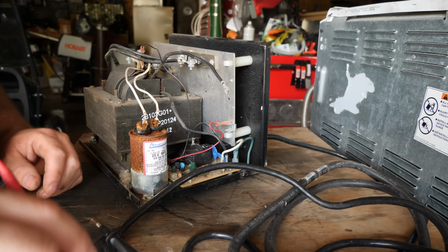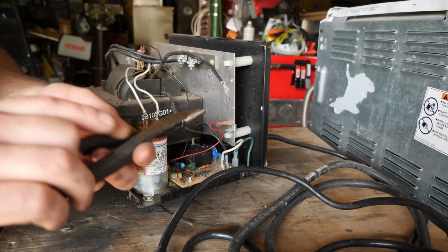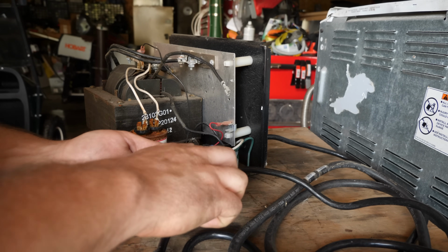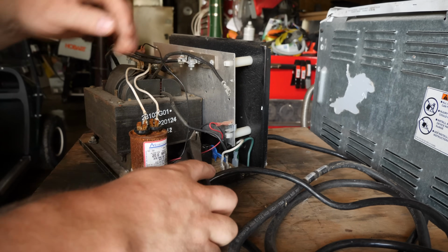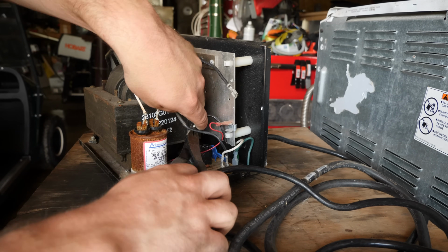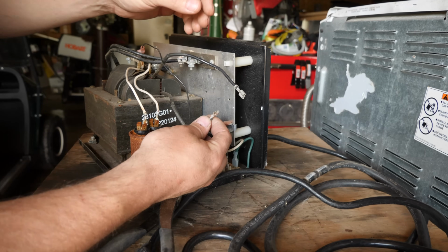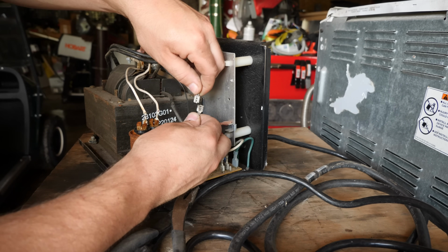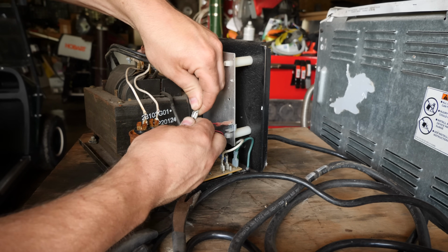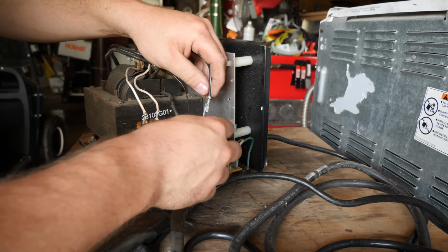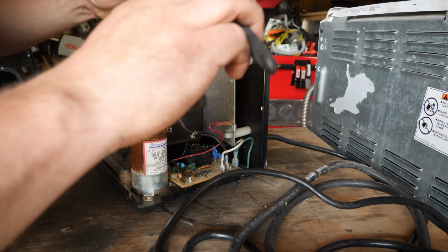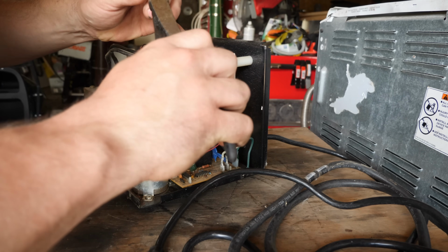Now what I'm going to do to test, because I bet you this control board is shot, I'm going to bypass our relay. I'm going to do that by taking our 120 volt cord input and just basically plug it in directly to the transformer. We're going to make this a tighter connection than it is so we don't have any arcing.